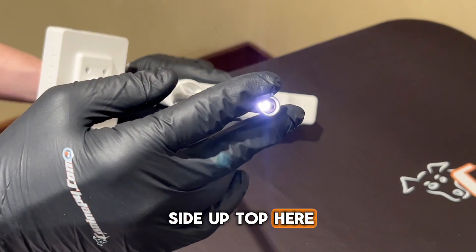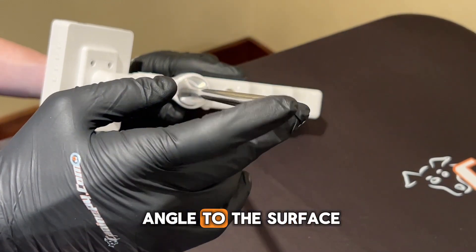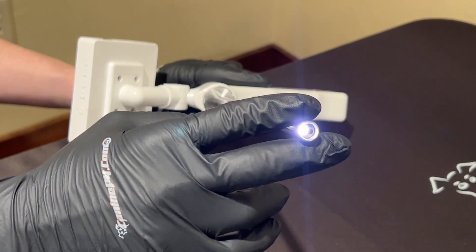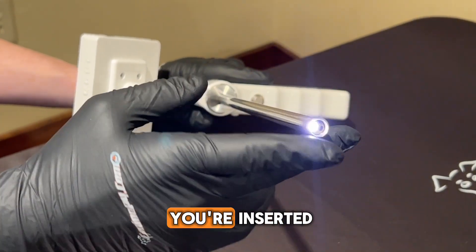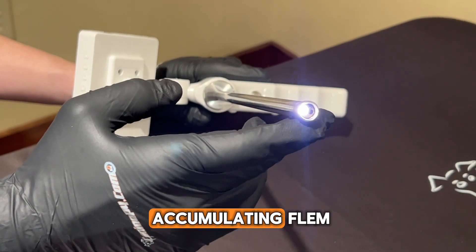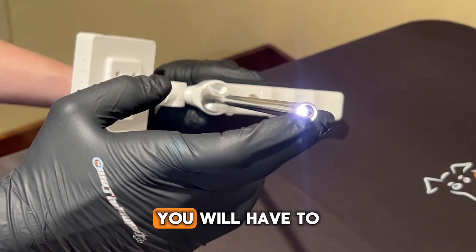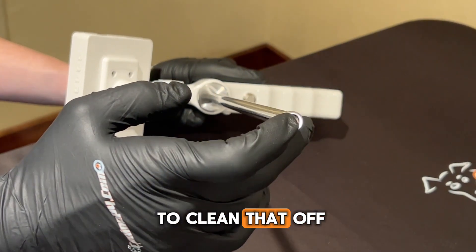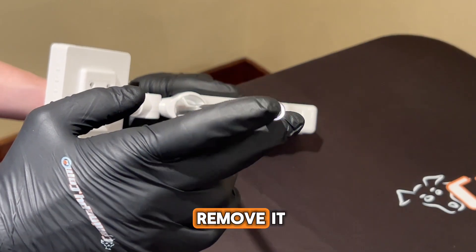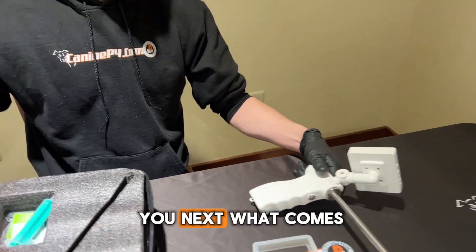On the far top side is where the air pump pushes air through at a 90-degree angle to the surface of your screen. The air pump is intended to remove phlegm, liquid, and other buildup from the camera as you're inserted. However, it's usually best to try to avoid accumulating phlegm or mucus on the camera to begin with. In many cases you will have to remove the AI probe to clean it off using a Q-tip, as the air pump isn't always sufficient.